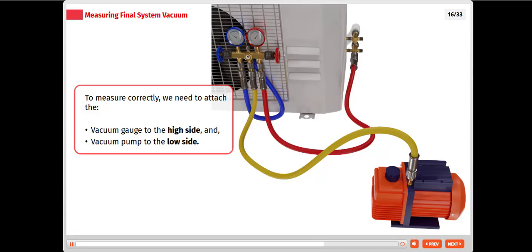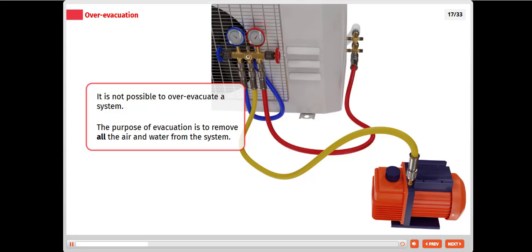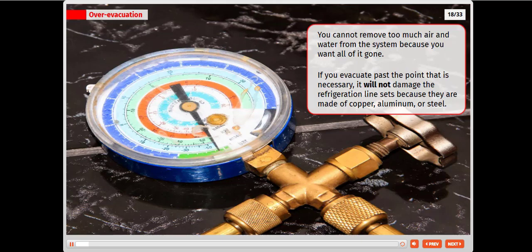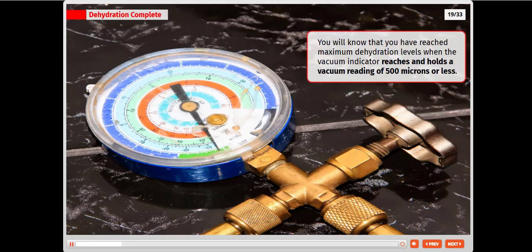It is not possible to over-evacuate a system. The purpose of evacuation is to remove all the air and water from the system. You cannot remove too much air and water from the system because you want all of it gone. If you evacuate past the point that is necessary, it will not damage the refrigeration line sets because they are made of copper, aluminum, or steel. You will know that you have reached maximum dehydration levels when the vacuum indicator reaches and holds a vacuum reading of 500 microns or less.